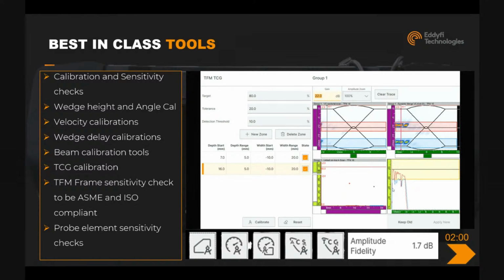So by now pulling back the probe slowly, I can see the attenuation of the signal. I move it forward and back, and the more precisely I do this, the better the result I get for my TCG calibration. As soon as I've done this, I click calibrate, and automatically the system has now calibrated the two holes in my block. This is a standard block. It's not a block which you would normally use, but it's a standard block that I have. But you can see that the responses are now nicely within the grid, the yellow bar here, making sure that all the responses are approximately at 80%. So that is how fast you can do a TCG calculation. And this is one of the many features and tools for calibration within the Cipher unit.